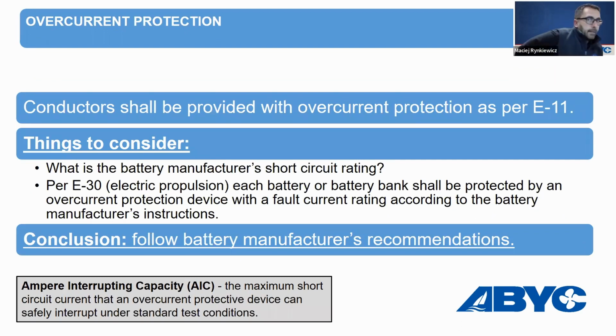Overcurrent protection. So basic E11 requirements would apply here. There were a few confusions here because often a BMS contains an internal circuit breaker, but that circuit breaker is there just to protect the BMS and internal electronics of the battery. It's not intended to protect the conductor, because the battery manufacturer doesn't know what size of conductor you have on the boat. Therefore, you need your regular overcurrent protection to protect the conductor, to protect the battery cables.